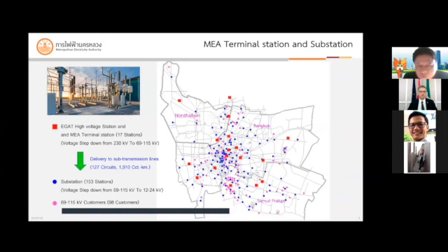This picture shows MEA terminal station and substations. EGAT high voltage station and 17 MEA terminal stations will step down voltage from 230 kV to 69 and 115 kV to transmit power to the sub-transmission lines to the 153 substations and 69 and 115 kV customers. You can see that the location and the distribution of the substations depend on the electricity demand, which is quite dense in the center of Bangkok.